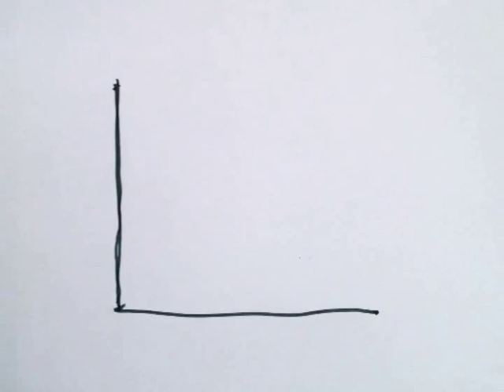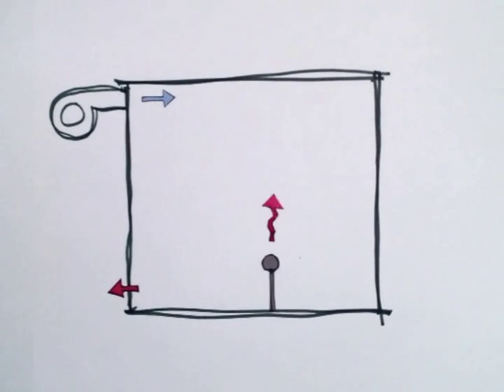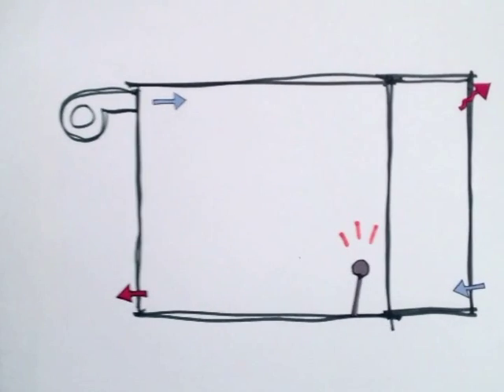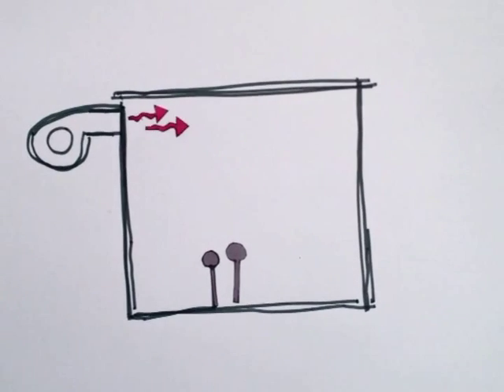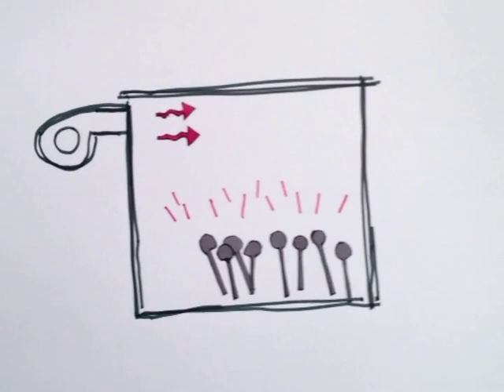The double facade, which is supposed to work as a buffer zone, is not working properly and does not have operable windows. The interior is mechanically ventilated and completely separated from the outside air. Also, the mechanical ventilation does not allow for big audiences. There is no correlation between the amount of people in the room and the air supplied.